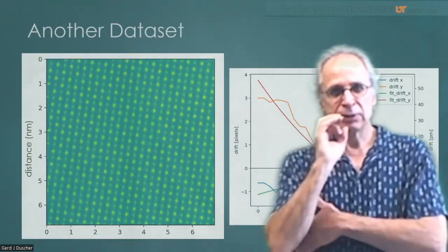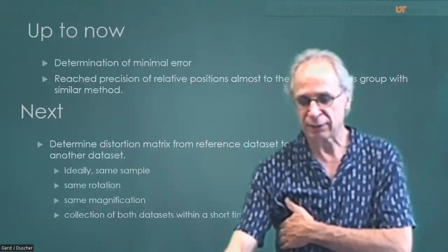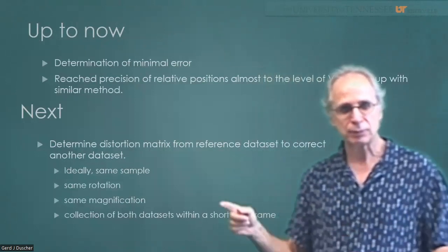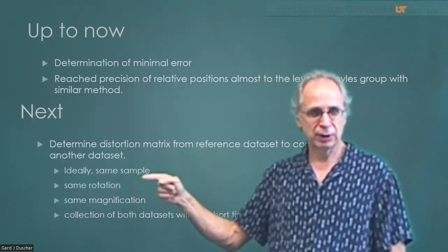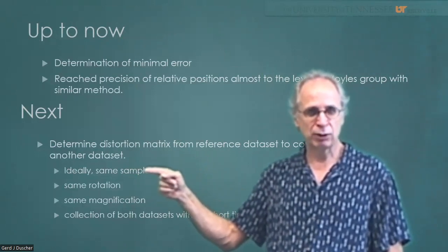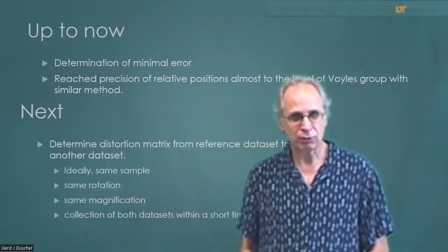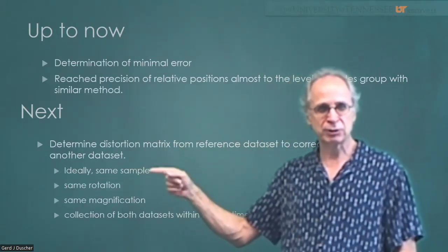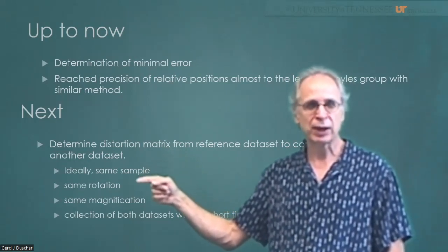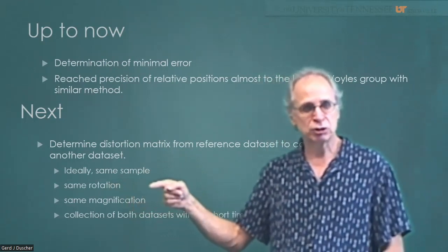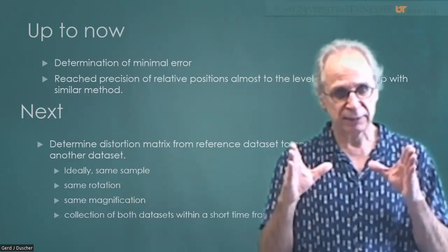One of the important points here, if you use another data set, is I wanted to go back to this one. If you take the sample out, what you usually have is a blanking on the very top of your microscope, so that will change possibly some of the electron optics. What you should not do is change the rotation of your scan.